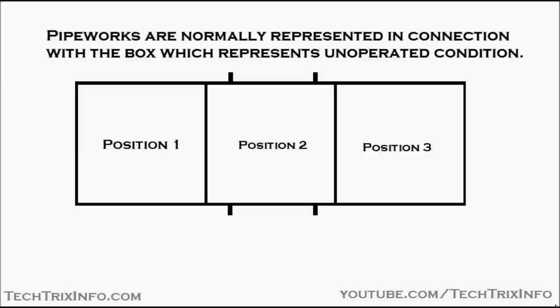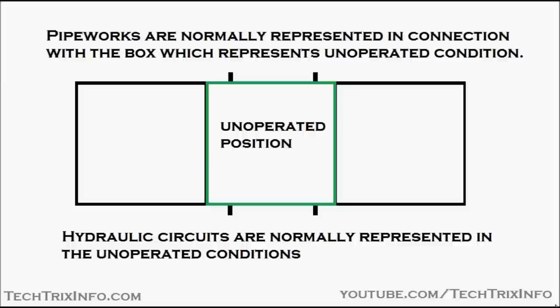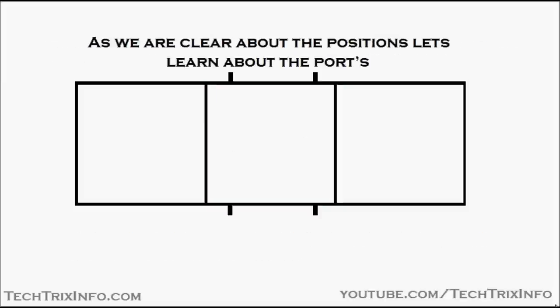The pipework is normally represented in connection with the box which represents the unoperated condition. The unoperated condition here is position two, where all the ports are blocked. Hydraulic circuits are normally represented in the unoperated condition, and the pipework is shown connected to that center box.